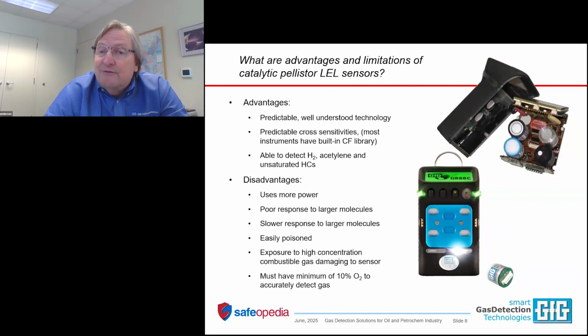So the most common type of LEL sensor by far is the traditional catalytic LEL sensor. The advantages are it's very predictable, well understood technology, predictable cross sensitivity, and most multi-sensor instruments that include a catalytic LEL sensor have a built-in library of correction factors. So you can change the measurement scale from natural gas or methane to pentane, if that's a more appropriate gas. If you're at a refinery, a lot of times the gases that you're going to be measuring are closer to pentane or hexane than they are to methane, so you can switch scales.